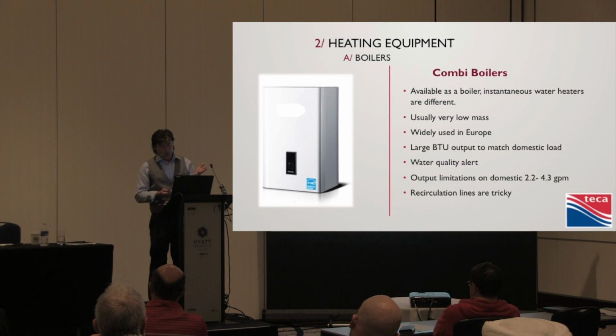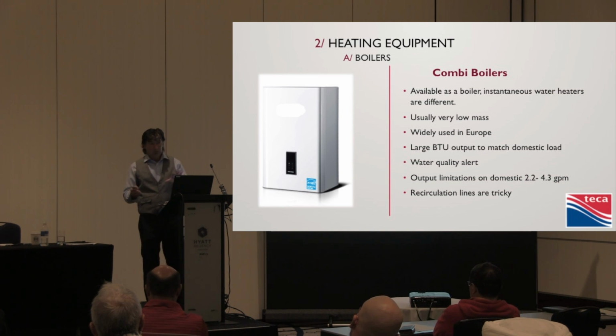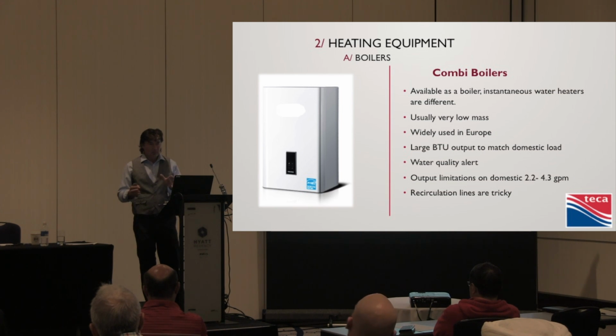The cost of it, once you add up the negatives here, and then throw on the tank on top of that. I mean, if it has to be done, it has to be done. And each of the manufacturers of these says how they'd like to have the recirc done. They know this is an issue and they've adjusted their controls accordingly. But the most widely accepted way is to add a storage tank. So to me, what we're doing is blending storage and instantaneous heating, which defeats the purpose.